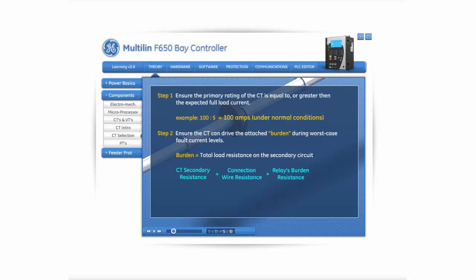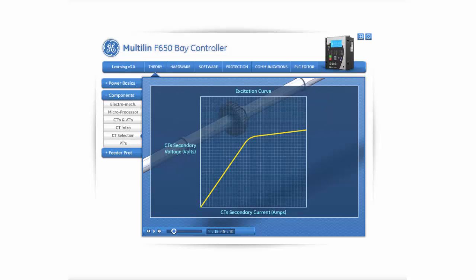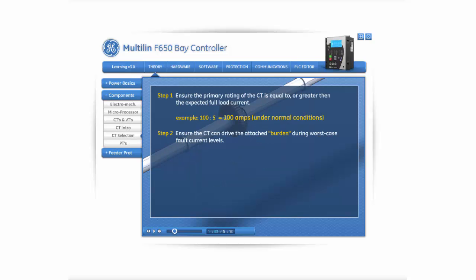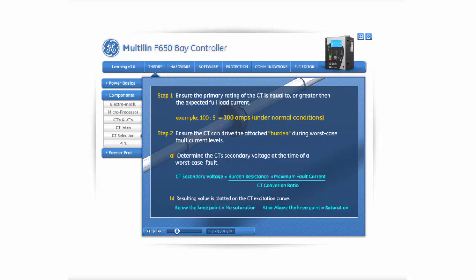As explained in the previous section, a CT becomes saturated when the secondary voltage reaches the knee point of the excitation curve. To determine whether the CT can drive the attached burden under worst-case fault conditions without saturating, we must determine what the CT's secondary voltage will be at the time of this fault. The CT secondary voltage at the time of fault is equal to the burden resistance times the maximum fault current divided by the CT conversion ratio. The resulting value is then plotted onto the CT excitation curve. If the value plotted on the curve is below the knee point, then the CT will not saturate under these worst-case fault conditions. If the value is equal to or greater than the knee point, then the CT will saturate.